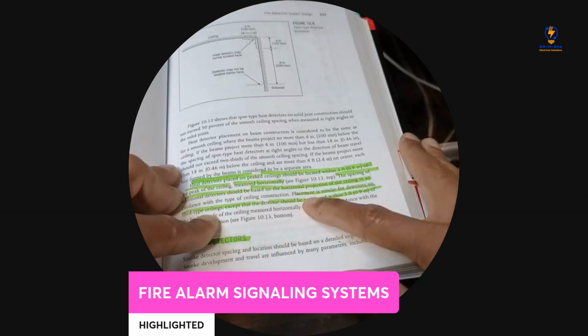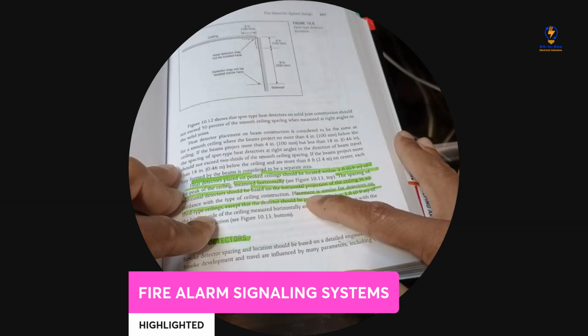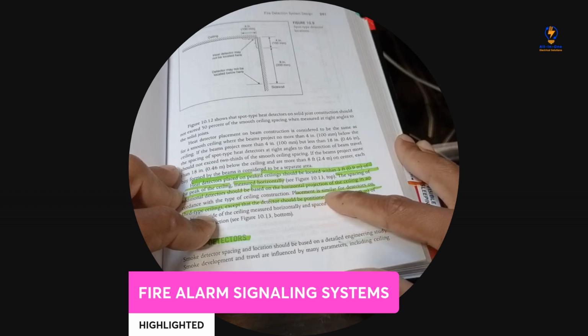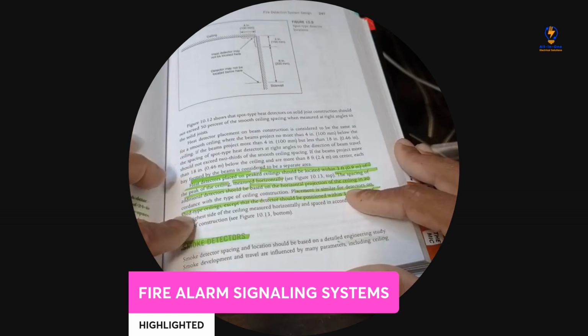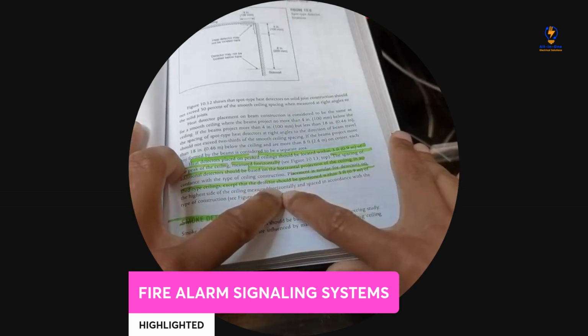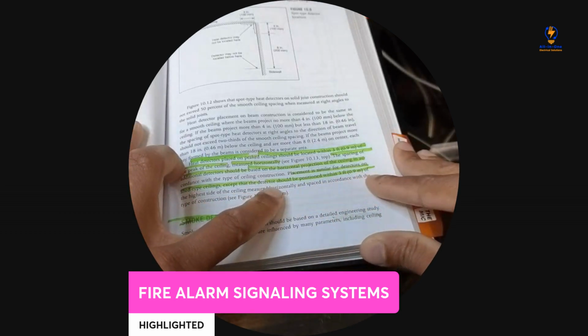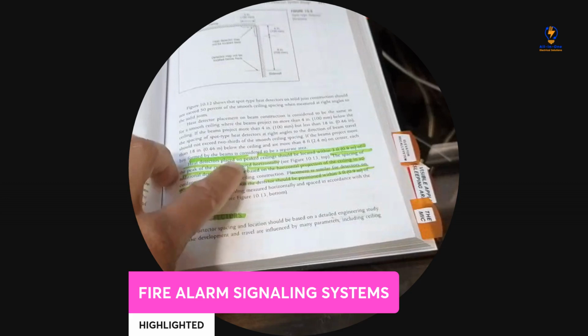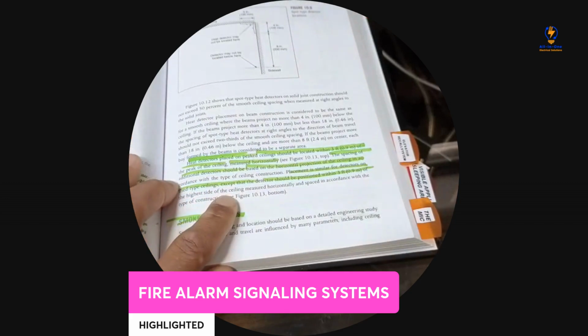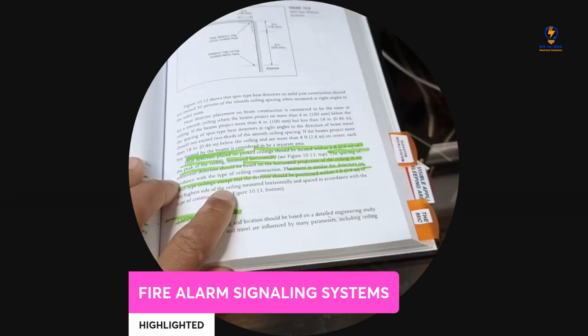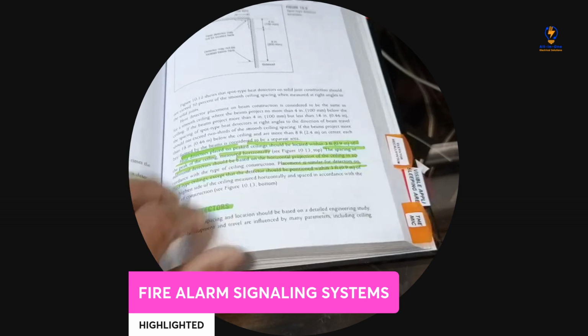And then as you see, if we read down this paragraph, placement is similar for detectors on shed type ceiling, except the detector should be positioned within 3 feet. See, they're similar. Horizontal for peak is 3 feet. In shed, the position is 3 feet. Okay.